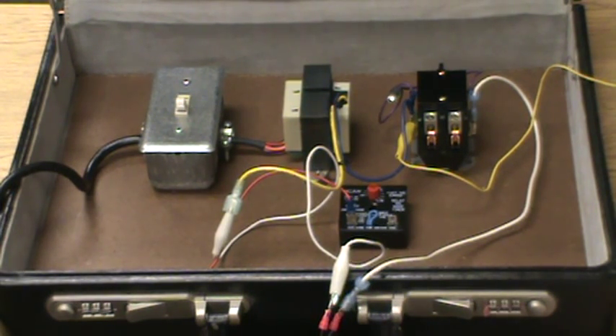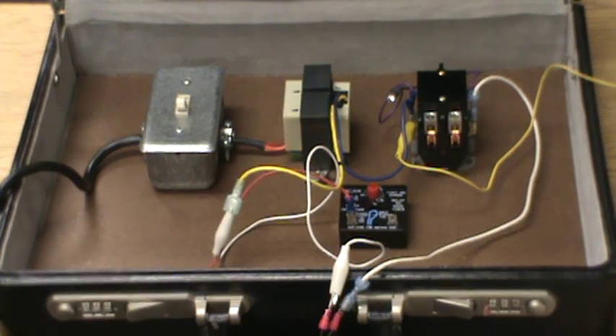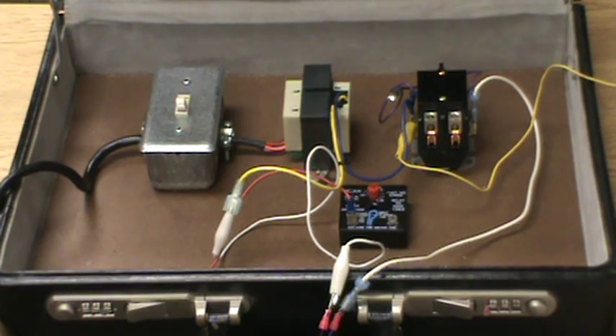Sometimes you can't find a short with the short pro because it's a different type of short. It could have been an intermittent short where the wires touched briefly and shorted out, or it could have been an electrical storm that blew the fuse on that furnace, or even an inrush of power where too much current draw can blow a fuse on the circuit board.